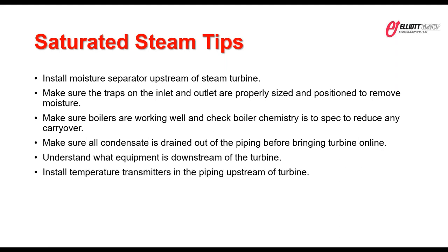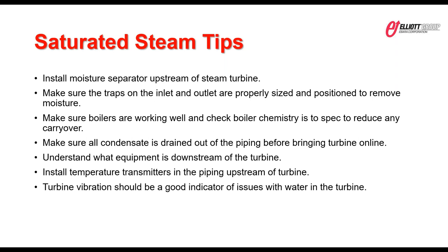Temperature transmitters, certainly those sorts of temperature instrumentation in the piping helps. You can know kind of where you are right at that saturation line, because you will have slight pressure drop and temperature drop from the boiler to the turbine, depending how far things are away. And then something we would provide is vibration. When you have vibration monitoring, and you start to see spikes in the vibration, then that's a pretty good indicator that something may be going on with the unit. You could have water in the turbine and it's causing some issues.